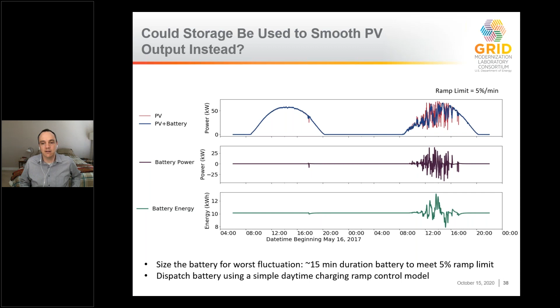The battery's capacity was sized similar to the PV plant—in this case a 75 kilowatt PV plant with a similarly sized 75 kilowatt battery. But the energy it needed to store was relatively small: at full power, it would be completely discharged in 15 minutes, which was sufficient to cover all conditions, including the partly cloudy day with rapid output changes from passing clouds.